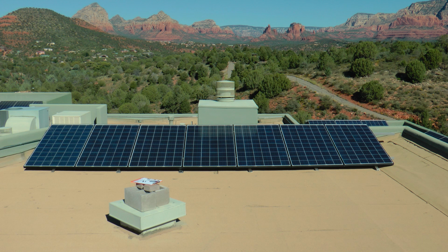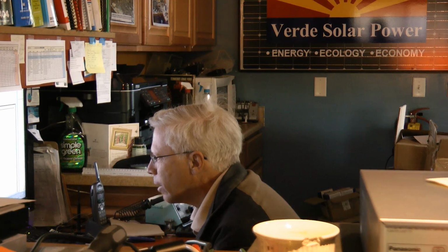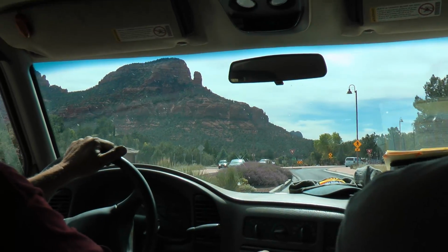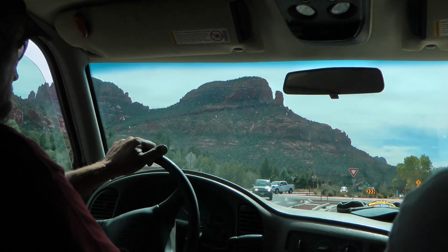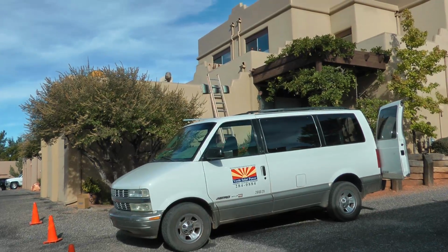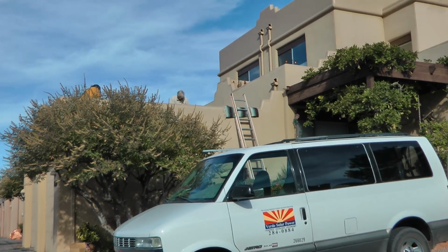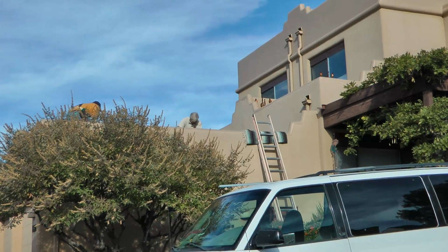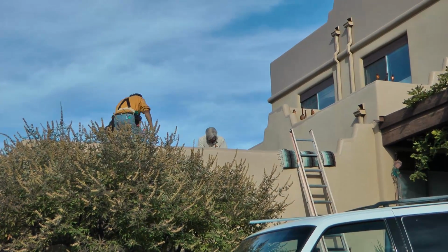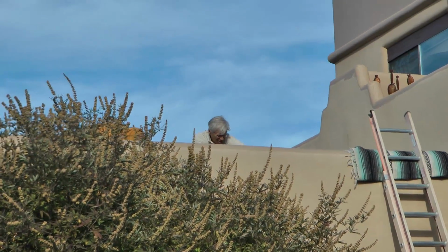Exactly. And if you look at the plaque, sometimes they'll show the short circuit current as 22 amps. Well, that's the ampacity, not the short circuit current. You're having two strings go through that DC disconnect so they're both 8.73. You don't add them together unless you combine them.